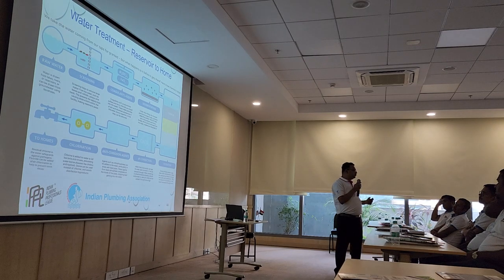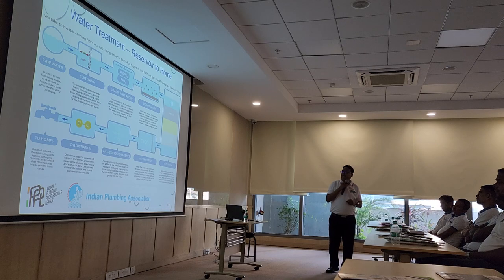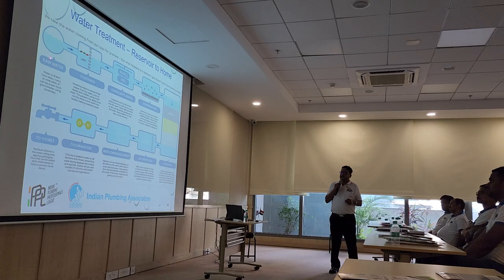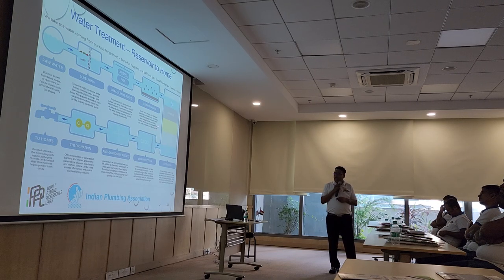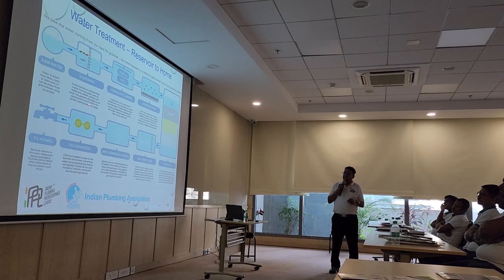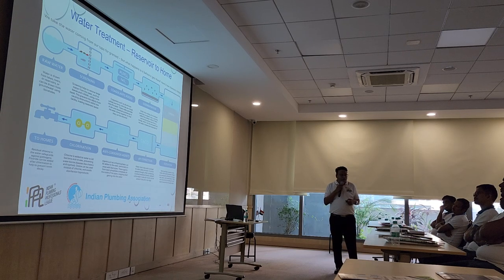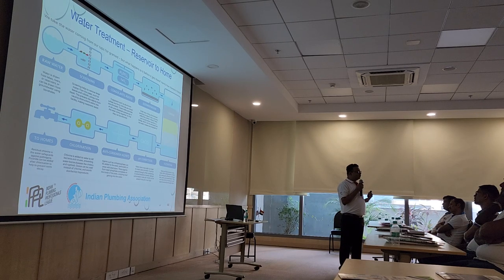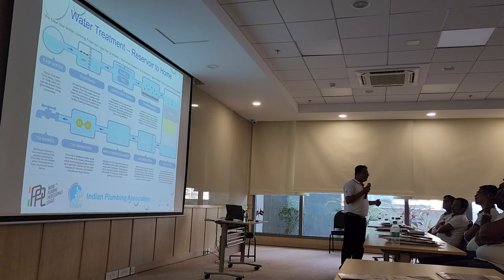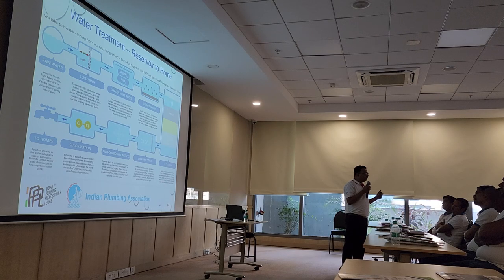Most of what we discussed so far was for building-level filtration units. When city-level treatments are there, the treatments are a little different. Raw water is collected, coagulation is added, sedimentation is allowed, then a carbon-sand-and-gravel filter is used, pH correction is done, anti-corrosion agents are added, fluorination is done, and then it is distributed. City-level water treatment plants are very beautiful — there are trickling filters, cascades, clarifying flocculators, and you can see the scale of the plant.